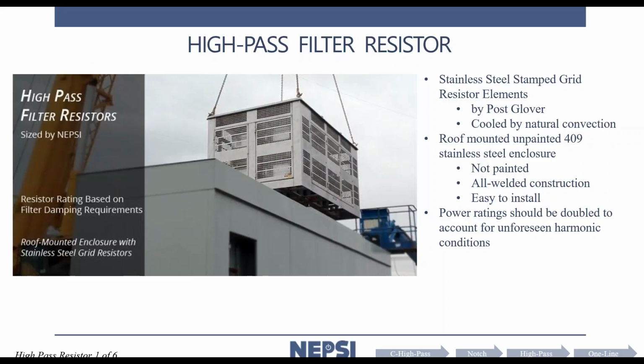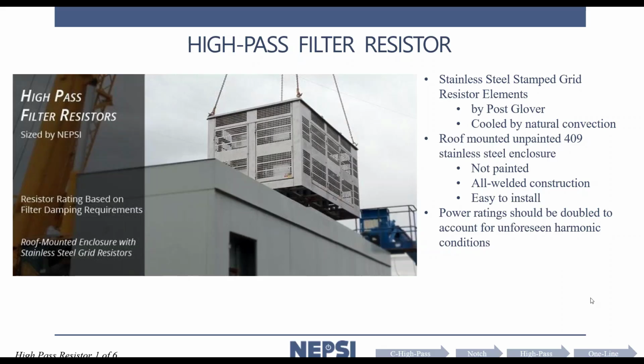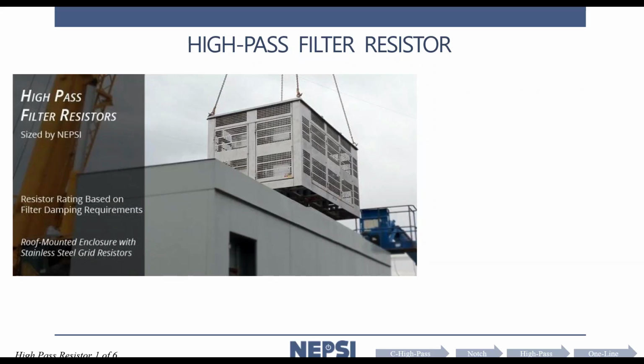It's from Rebecca Yitna, and the question is, if the voltage limits of 519 are met, but not necessarily the current distortion limits, is that a problem? The voltage distortion values are met, but the current distortion values are not. Correct. And I would say that within the plant itself, it is not a concern. The current distortion is not of concern. There is nobody evaluating that. Of course, if you have higher harmonic current distortion within the plant, you will experience more heating in the transformers and things like that, but this may be minor. The major concern is what is the voltage distortion, because that's impacting the rest of the facility.